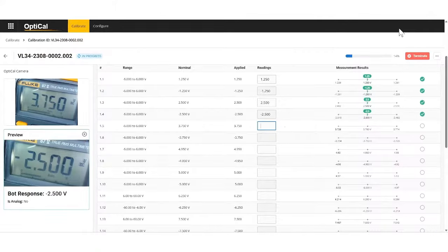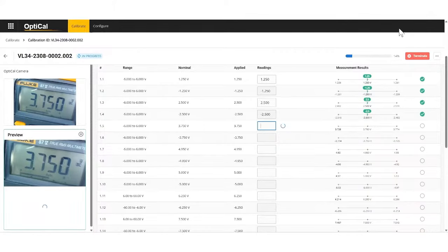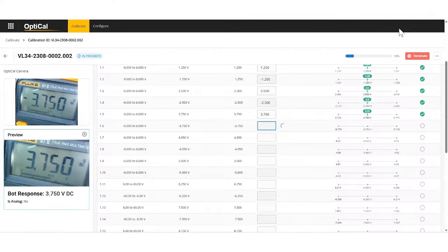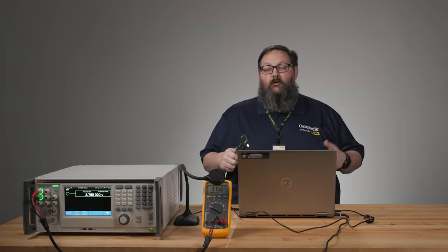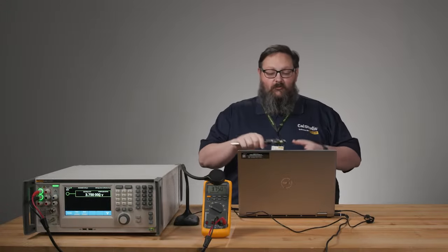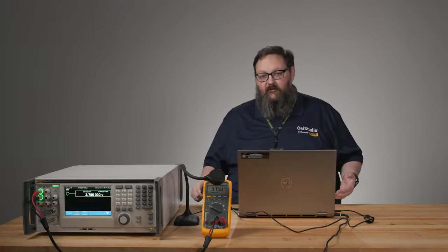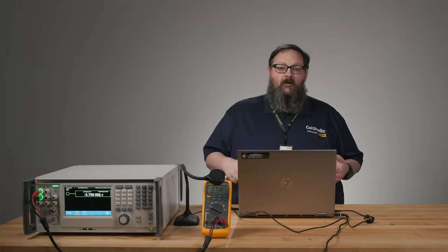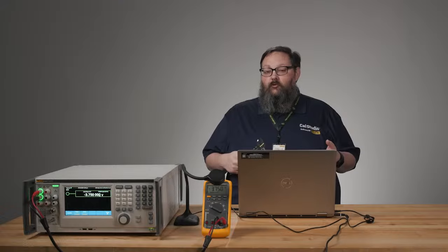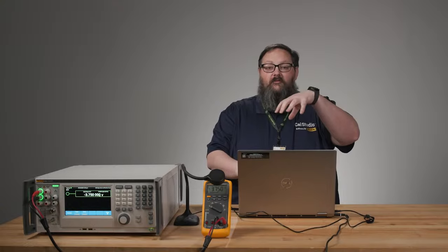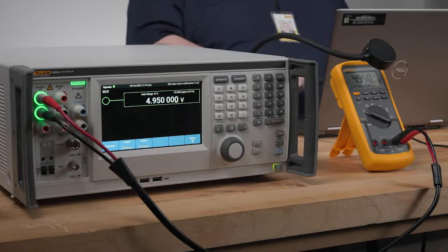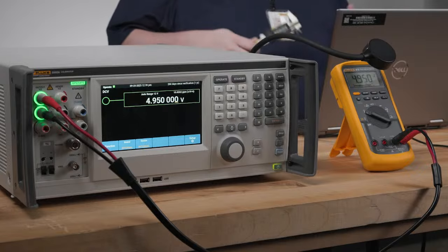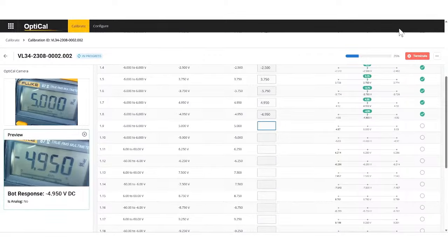And some other great examples of that is if you think about your calipers or your micrometers, where typically you're having to pick up the device, put your gloves on, pick up your gauge blocks, take the measurement, set it down, take off your gloves, type in the number. Instead, we will be able to, with a camera over the top of this process as I'm calibrating, give a voice command to capture that reading as a part of a procedure run in CalStudio. And all of that will again be integrated into that CalStudio execution environment.